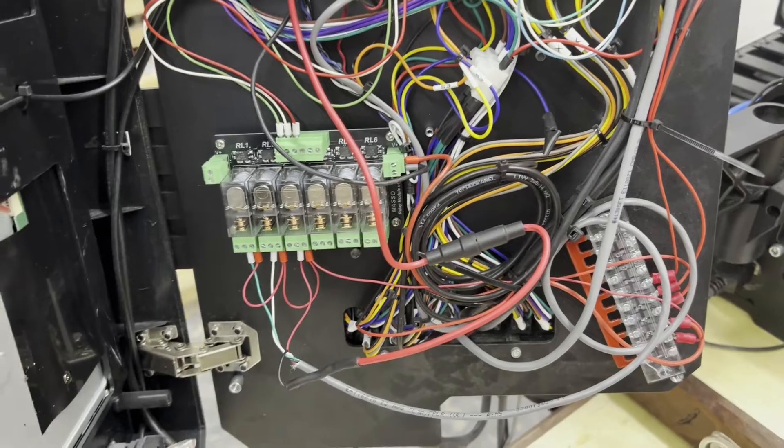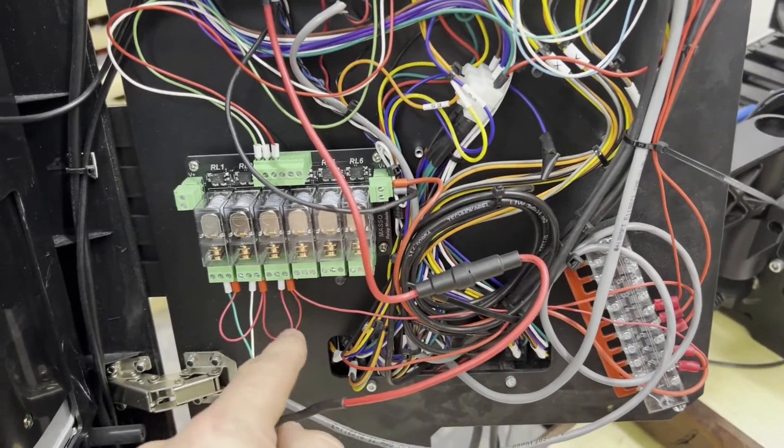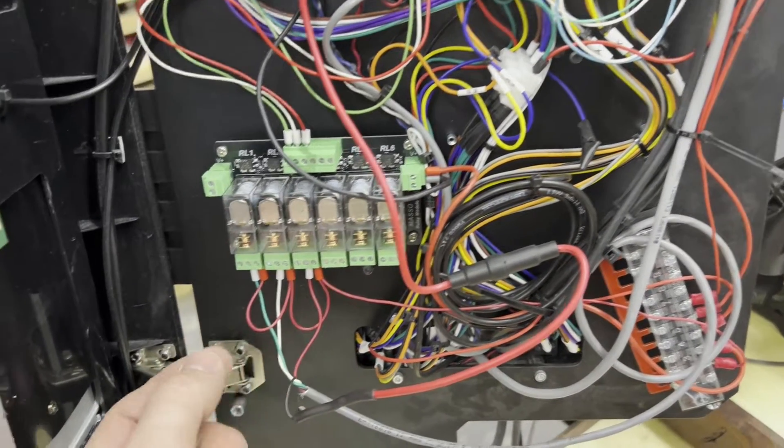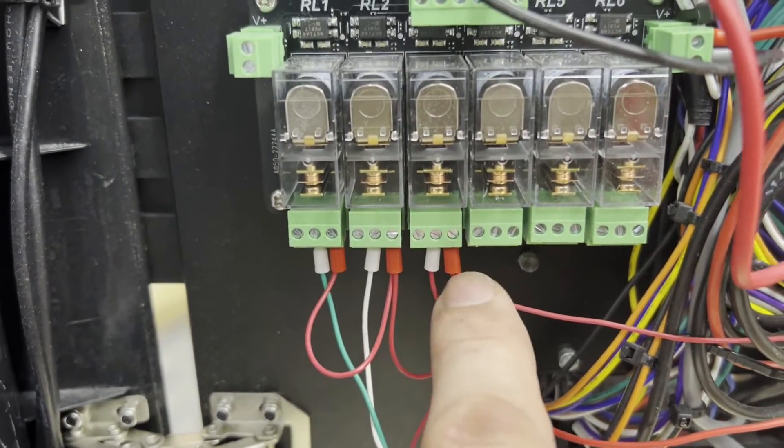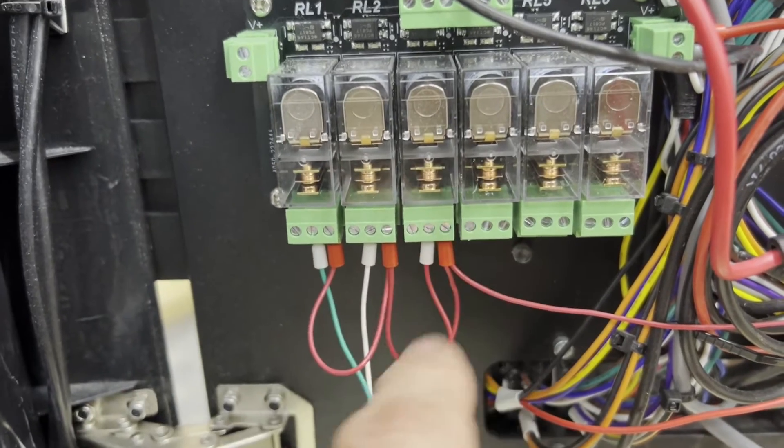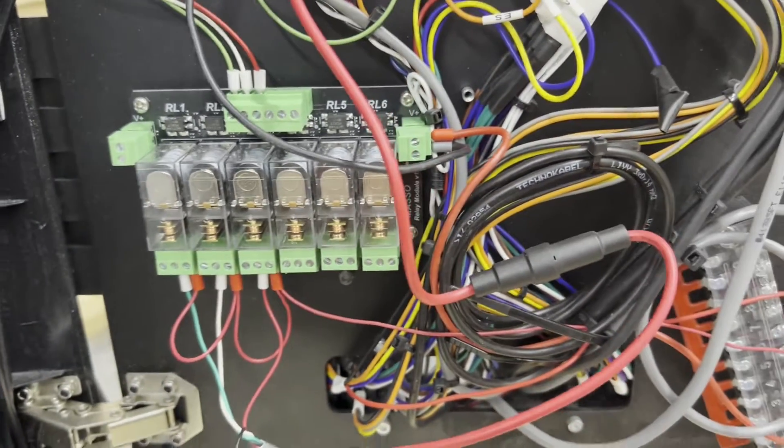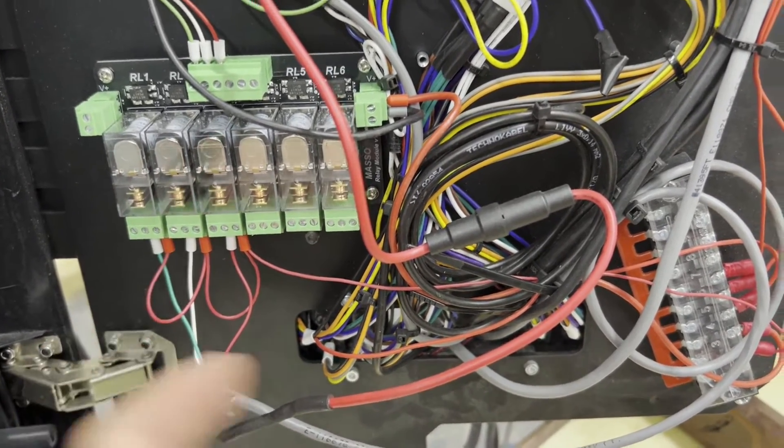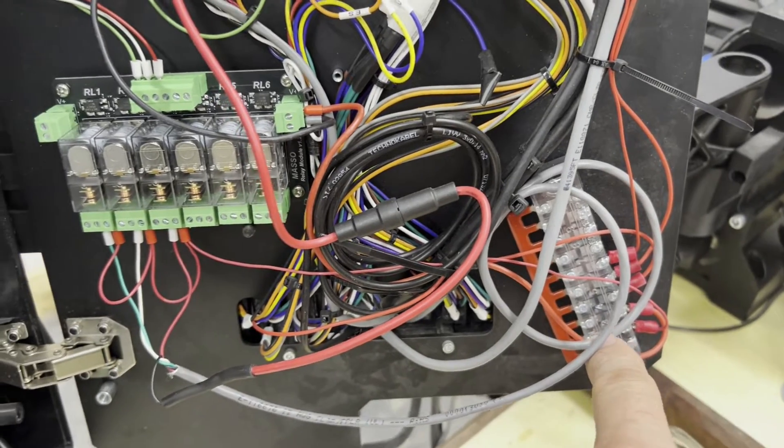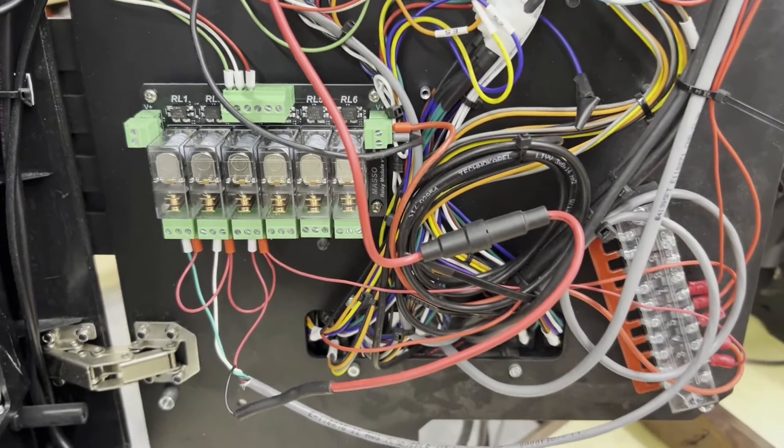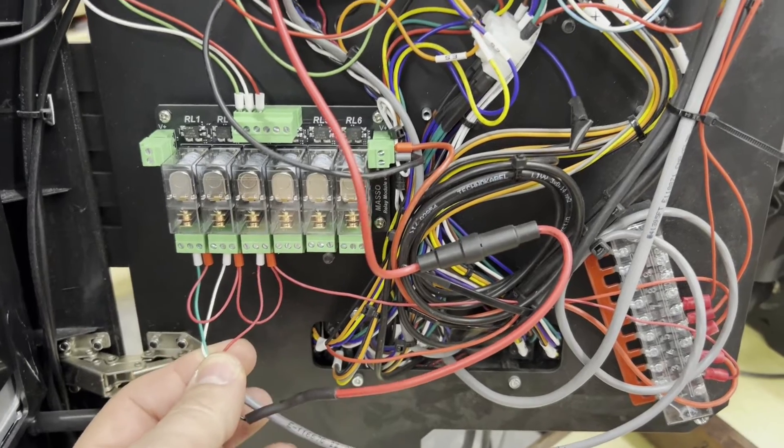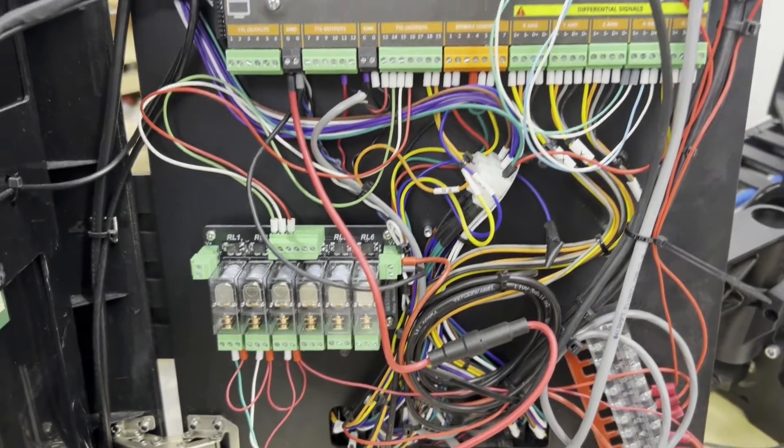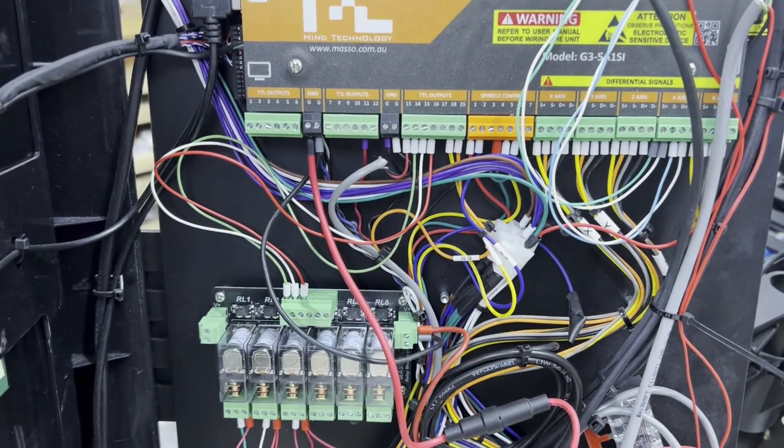Now, I took another wire off of my terminal block, and I jumpered it into the common here, so that on each of these relays. And if you look, I have two wires in that ferrule, two wires in that ferrule, and one here, because I just jumpered them across like that to use one connection off my terminal block. If you don't like that, you can run independent cables all the way back to the terminal block, and that would be fine, too. But there's really nothing wrong with this, either. It just saves me some wiring and some ports on that terminal block. So, now we have our light connected, and we're good there.